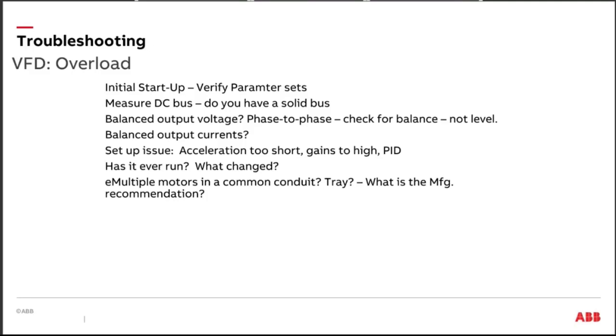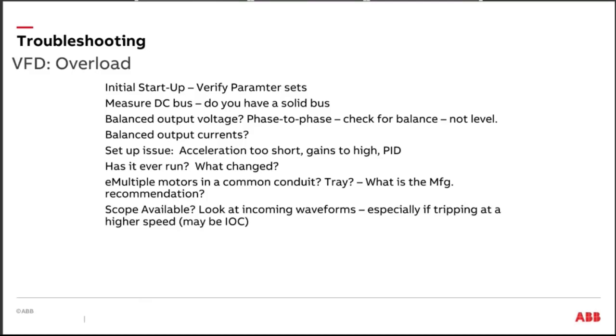Overload, very typical. I'm going to look and see how I've got my drive set up. I'm going to look and see how fast I'm trying to accelerate it. I am going to look and see what kind of application I got there. Okay. And then I'm also going to start looking on the mechanical side. How many motor leads do I have in my tray or in my conduits? Am I having a problem with that? If I have an O-scope available, it's always kind of nice to look at your voltage waveform to see what your voltage looks like coming into the drive. Especially if you got an application where you're having some current problems at the higher ends. Maybe I'm getting a little bit of flat topping on that input, and I'm a diode input drive. Maybe I'm using diodes in the front end. I'm using the traditional old 6-pulse diode front end drive, or an old 18-pulse, and I'm flat topping a little bit coming into the drive.